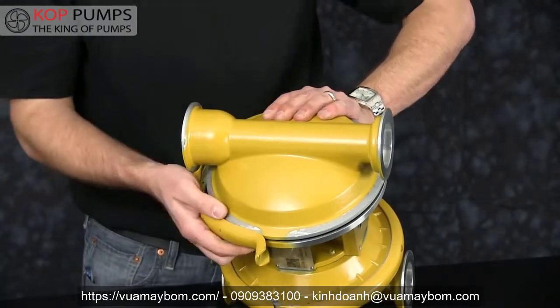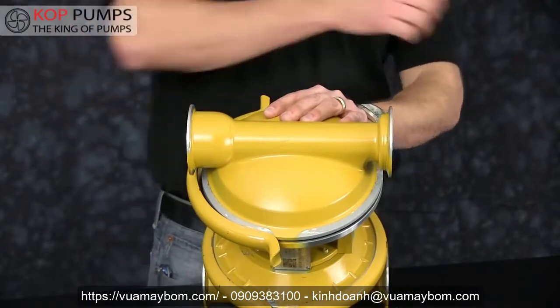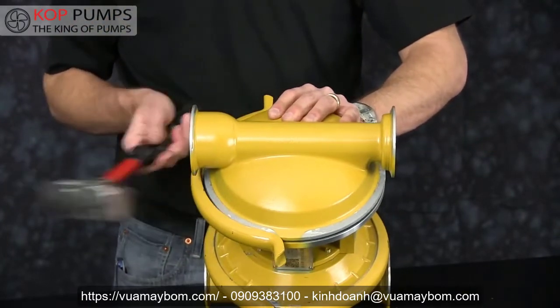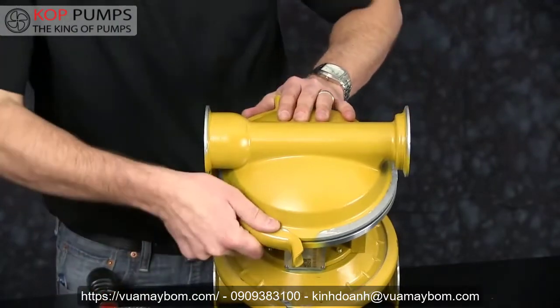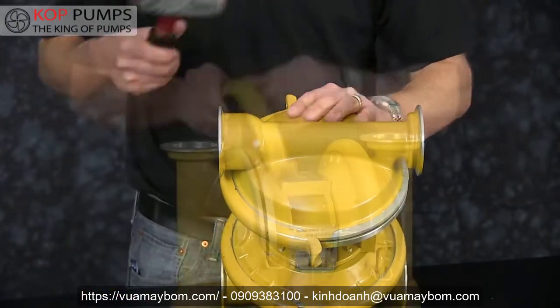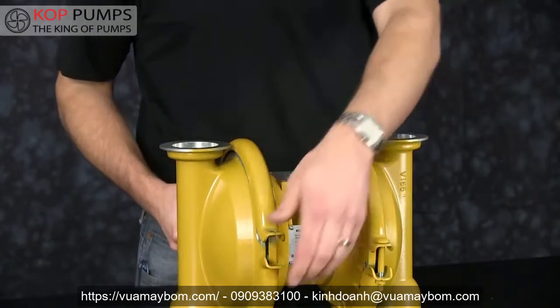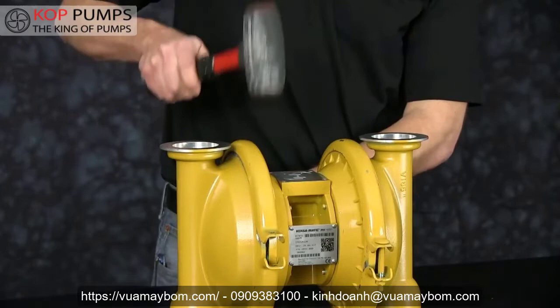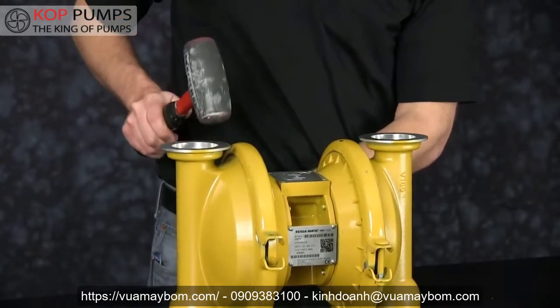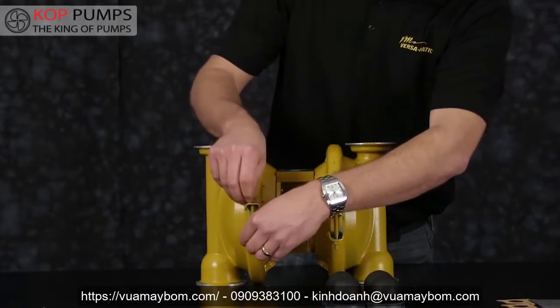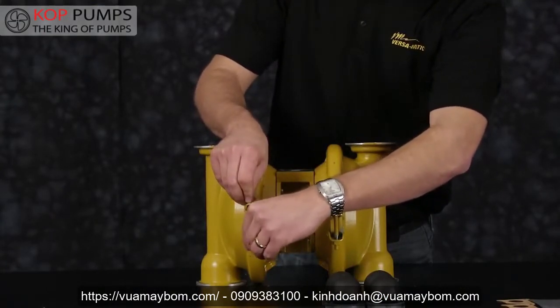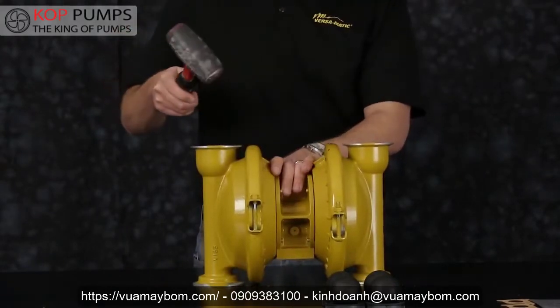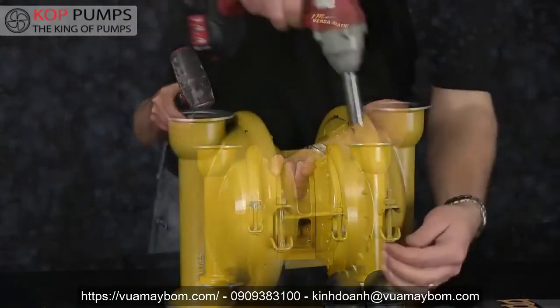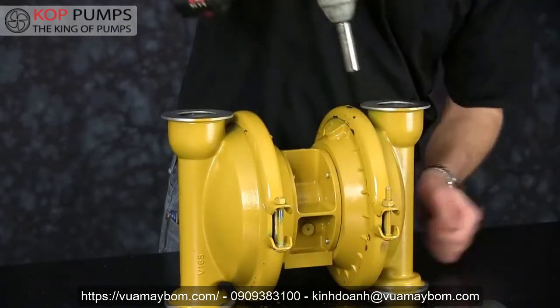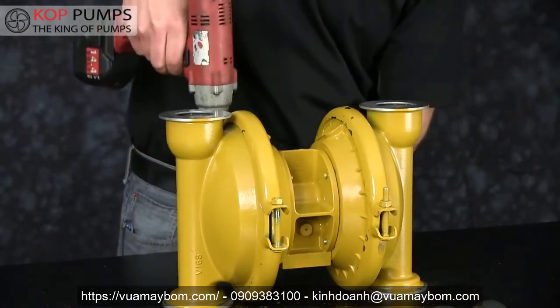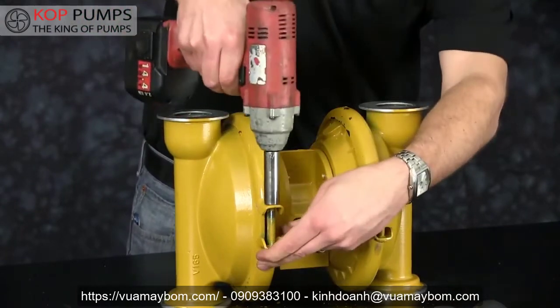Now we're going to install our opposite clamp band. Again, you may need a rubber mallet to tap on the clamp band assembly. Be sure to fully seat the clamp band assembly. Once you fully seat the clamp band assembly, go ahead and install the bolts. Once you get both clamps installed loosely, you may need to align the outer chambers in relation to the center of the pump. When you tighten the clamp band assemblies, there is no torque spec, but tighten them evenly.